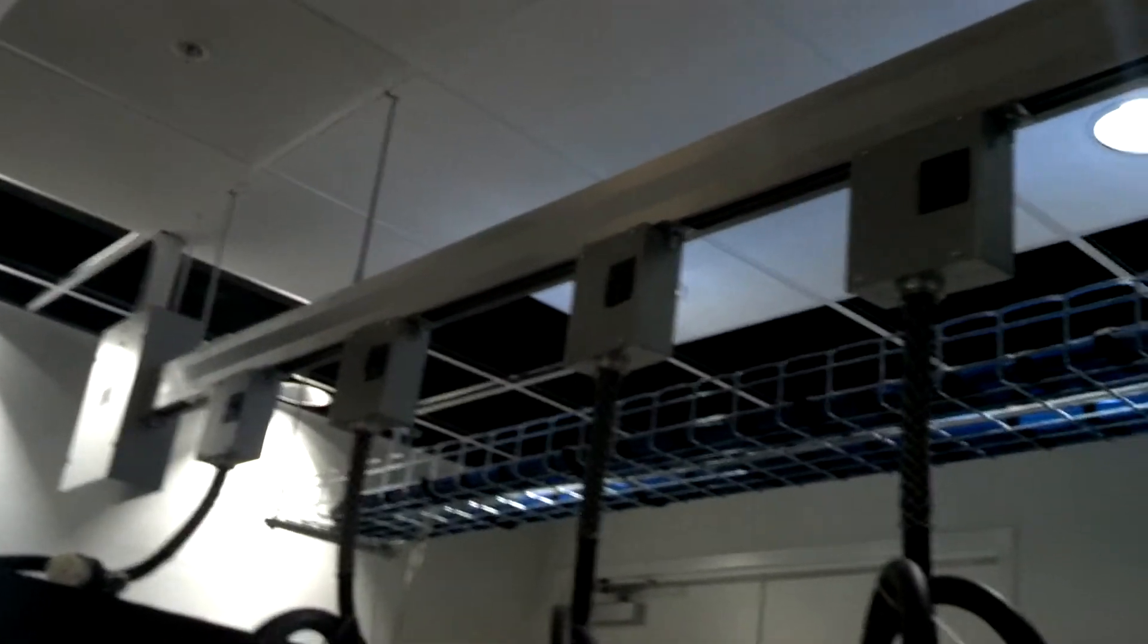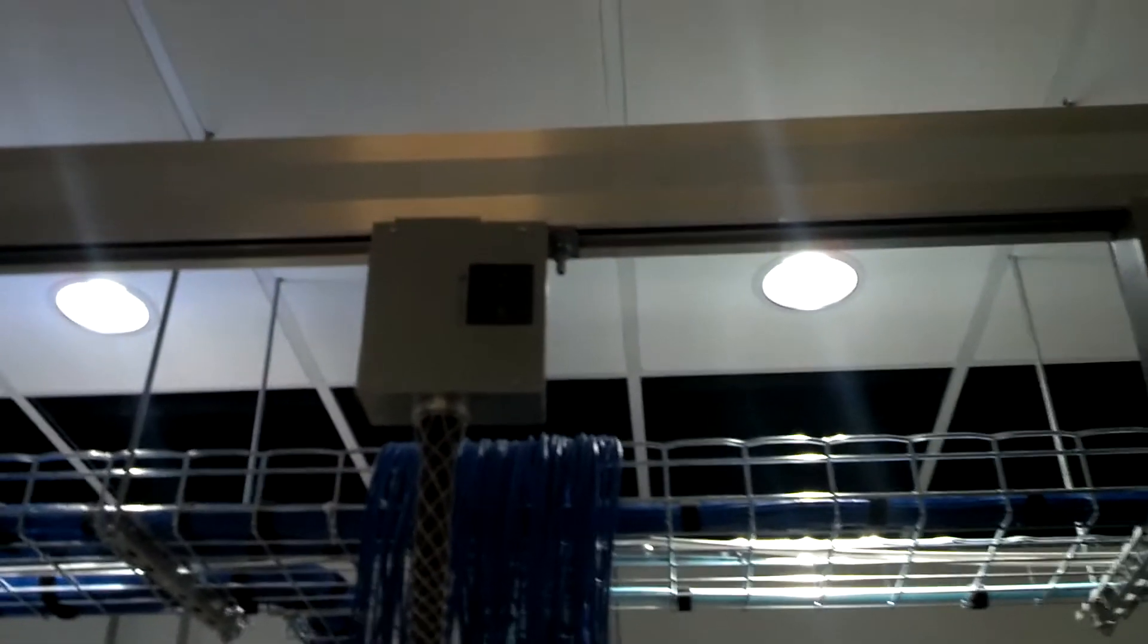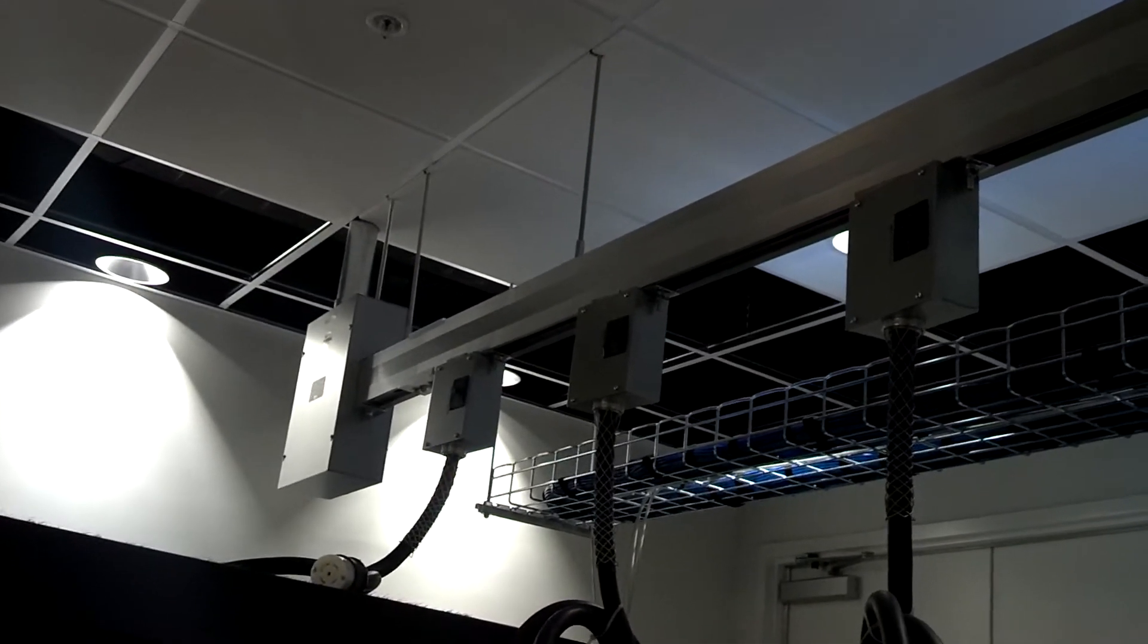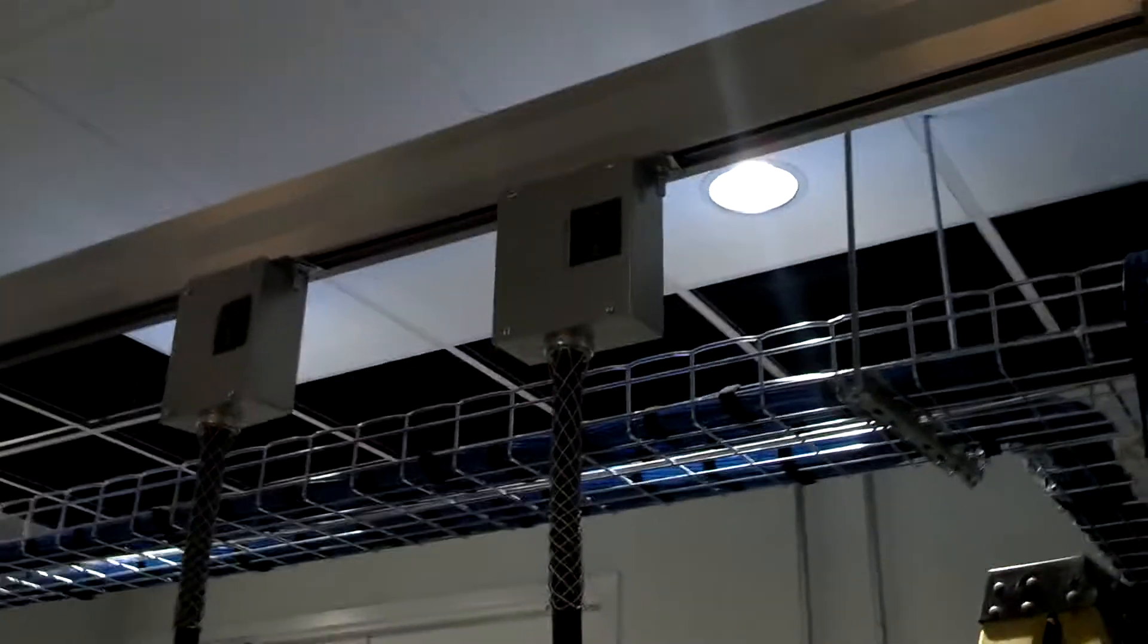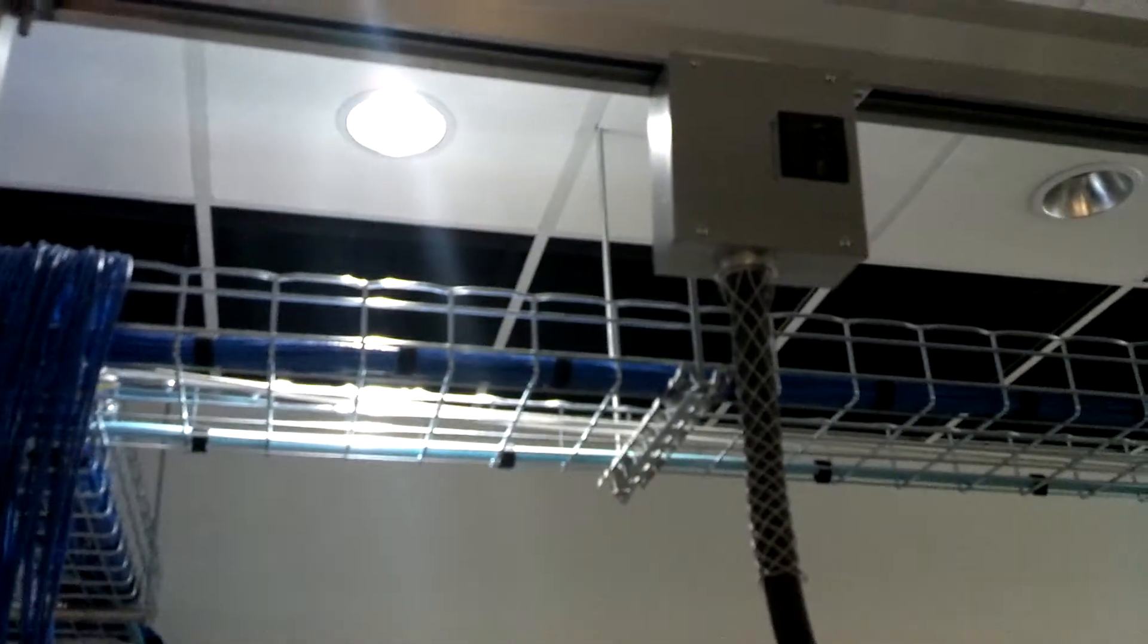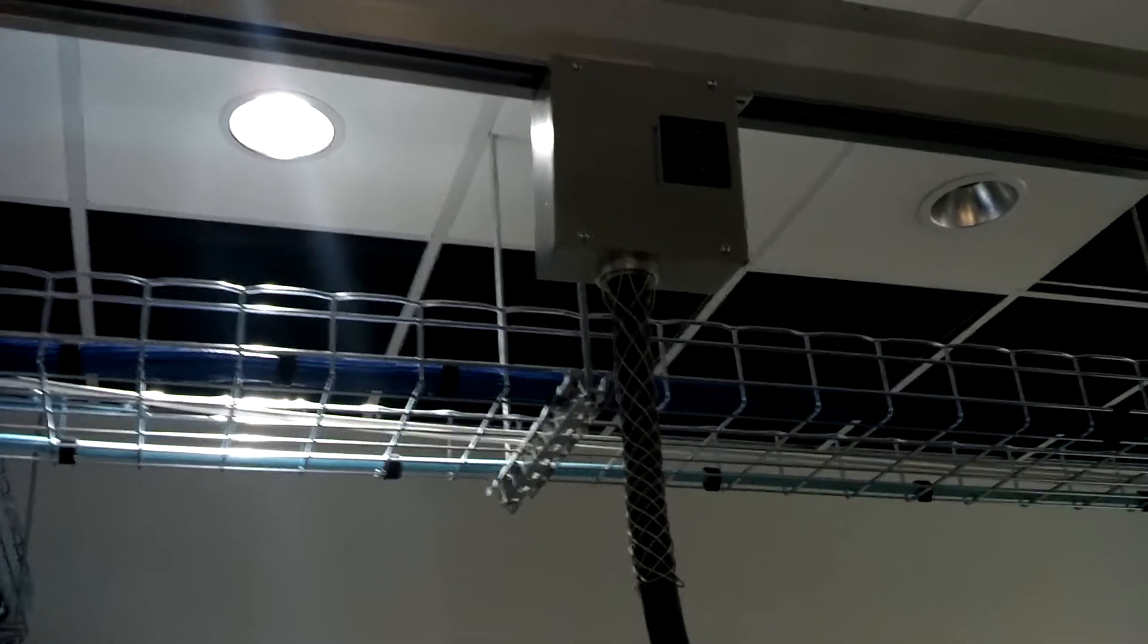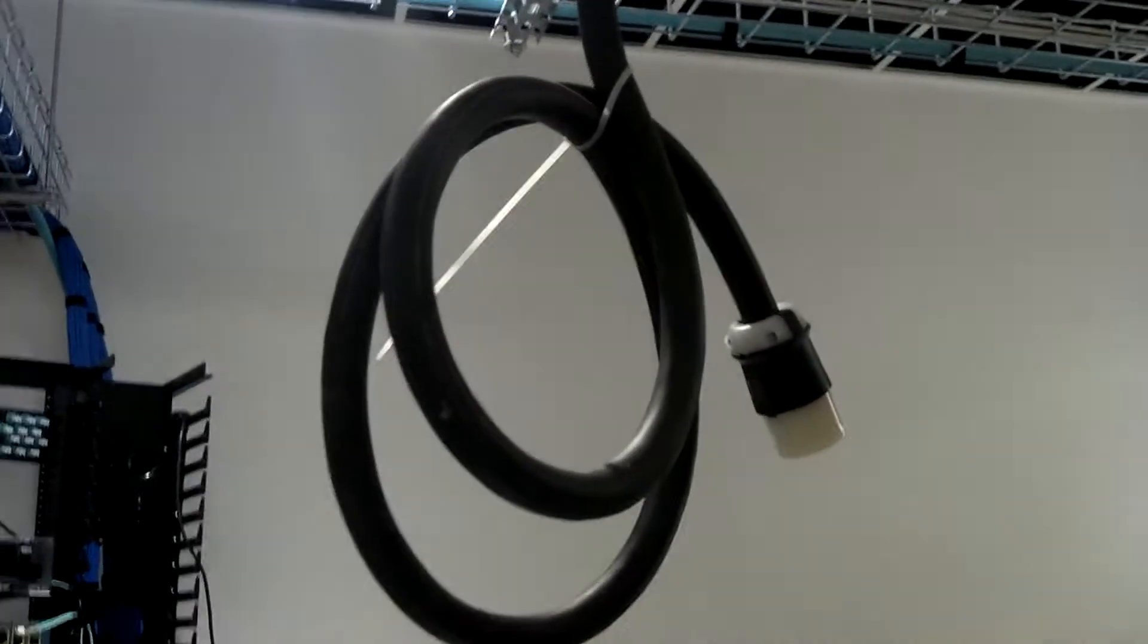But a couple other features in here. We'll notice that we have what's called rail power. So when you're powering a rack of servers, you need obviously a lot of power. And so it's common to see power distribution systems like we've got overhead in this room. This will allow us to move. You notice these boxes here each have plugs dangling from them. Each one of these boxes is going to support a single rack of servers. So in this case, we have 30 amp, three phase breakers per enterprise rack. So if you're not familiar with those terms, that's a lot of power. So let me continue the tour this way.